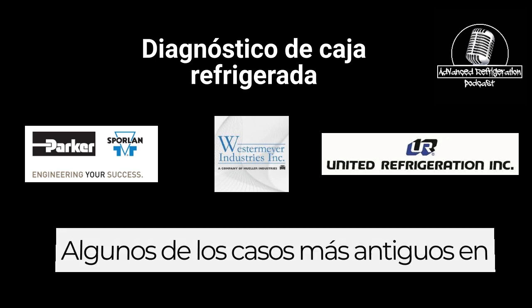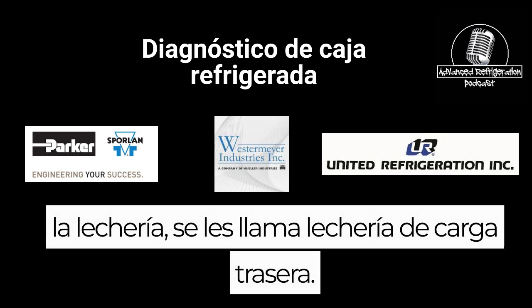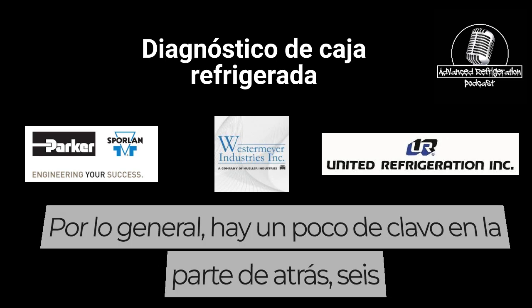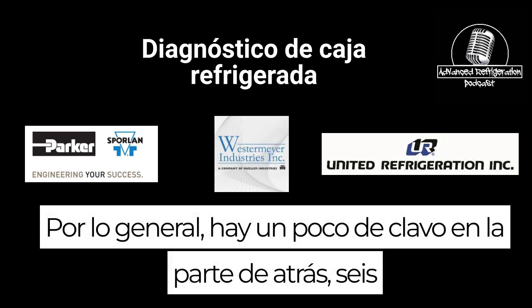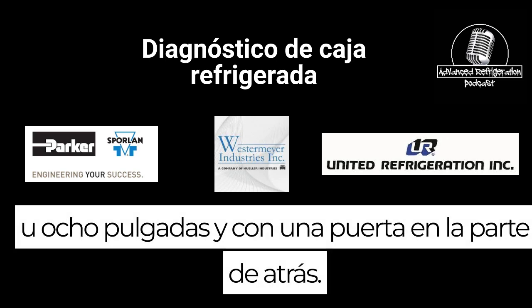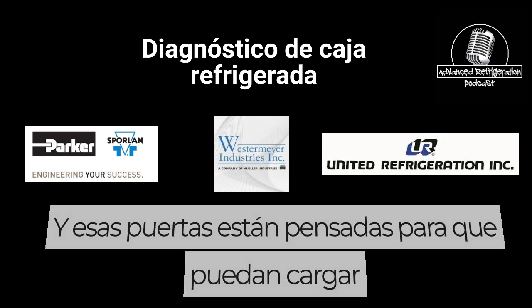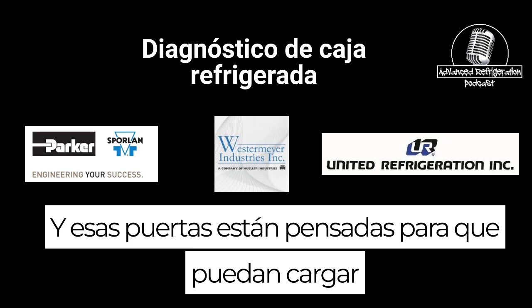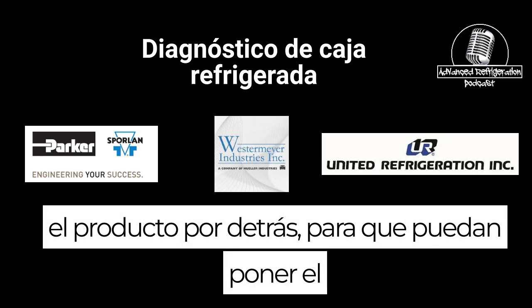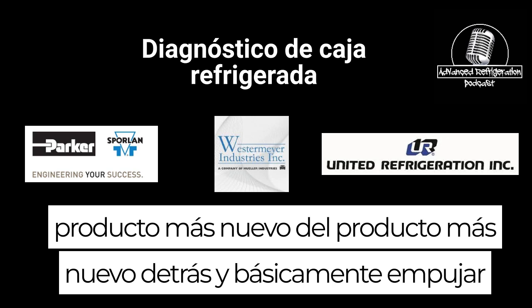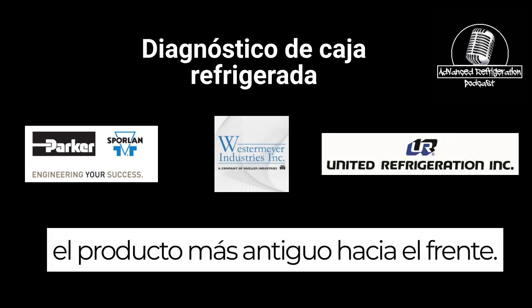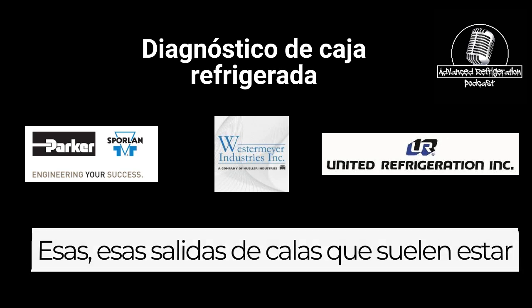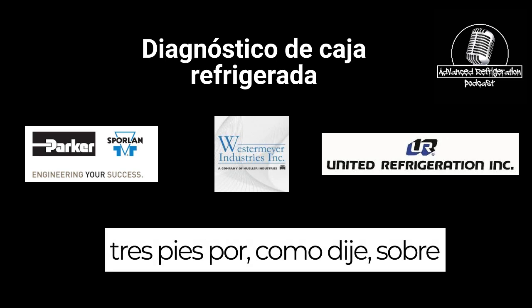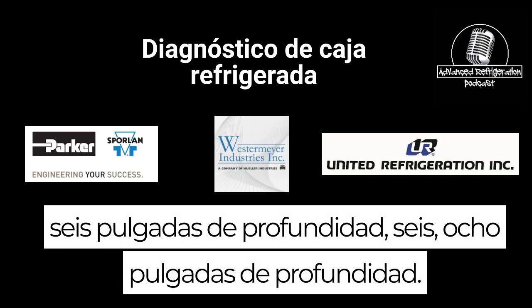Some of the older cases in the dairy, they're called rear load dairy. Usually there's a little alcove in the back, 6 or 8 inches, and with a door in the back. And those doors are meant so they can load the product from behind, so they can put the newer product behind and basically push the older product towards the front. Those alcoves are usually 3 foot by, like I said, about 6 to 8 inches deep.